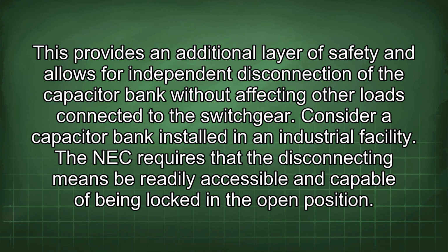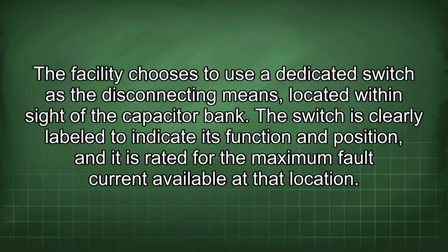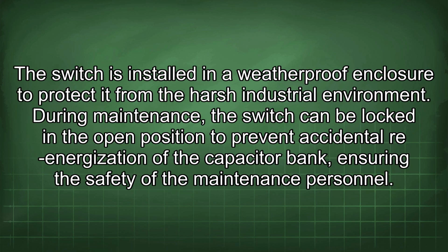Consider a capacitor bank installed in an industrial facility. The NEC requires that the disconnecting means be readily accessible and capable of being locked in the open position. The facility chooses to use a dedicated switch as the disconnecting means located within sight of the capacitor bank. The switch is clearly labeled to indicate its function and position, and it is rated for the maximum fault current available at that location. The switch is installed in a weatherproof enclosure to protect it from the harsh industrial environment. During maintenance, the switch can be locked in the open position to prevent accidental re-energization of the capacitor bank, ensuring the safety of the maintenance personnel.